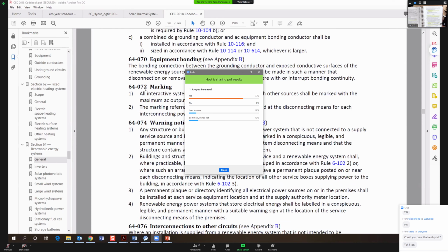Okay. So 64-072, marking. All interactive system points of interconnection with other sources shall be marked with the maximum AC output operating voltage and the current. So if you have an interactive system installed at the point of interconnection, you should provide the AC output voltage and the current. Also, the marking referred to in subrule 1 should be providing the disconnect means for each interconnected power source. So this is a rule talking about marking.